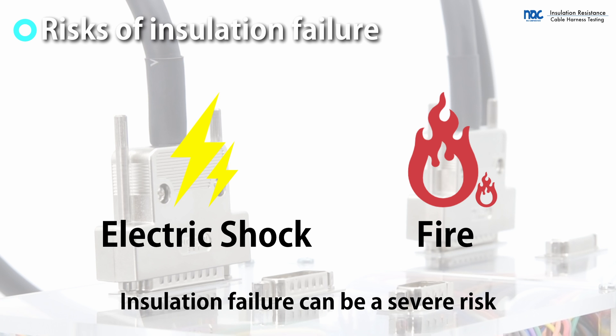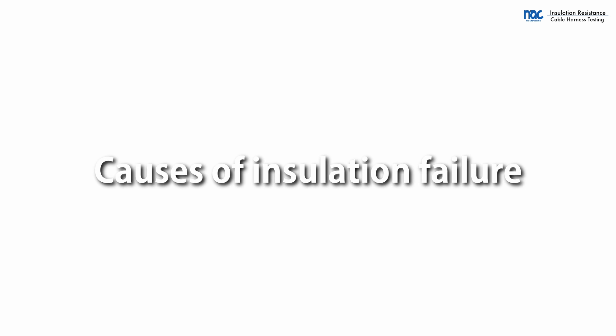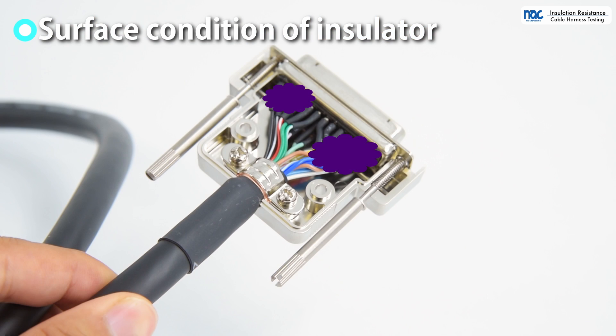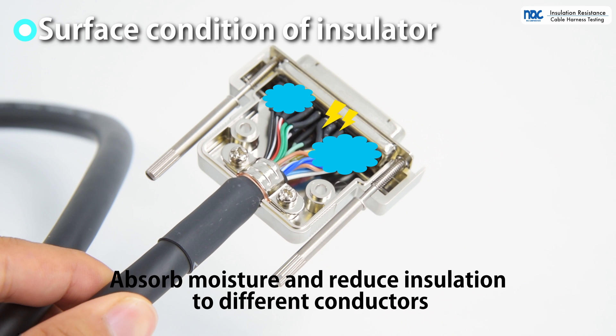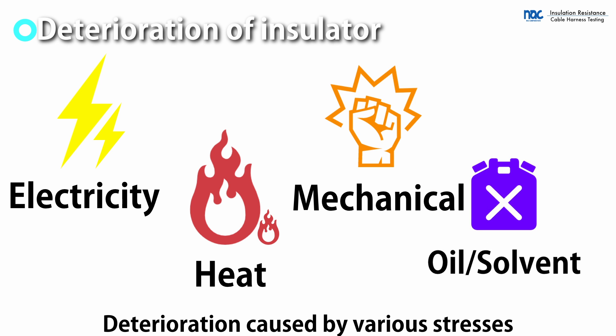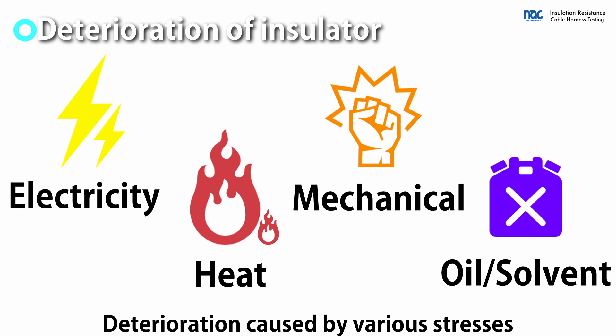Insulation resistance testing is aimed at detecting insulation defects. The surface condition affects insulation performance. Dust and dirt may stick to the harness processing part and inside the connector. These absorb moisture and allow electricity to flow easily across the insulator surface. Insulators deteriorate due to a variety of stresses, such as electrical stress, heat, and mechanical damage. Insulation is also affected by oil, solvents, and other substances.